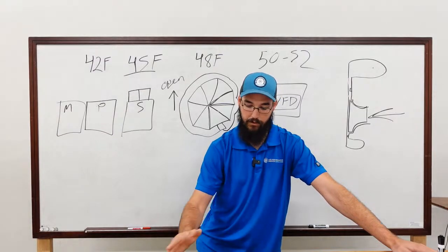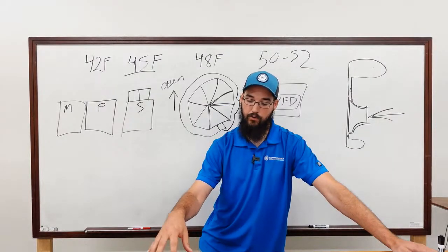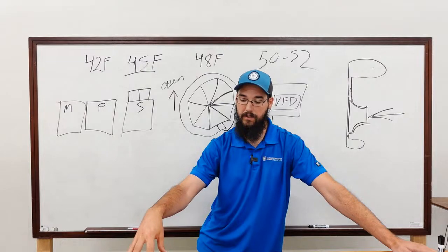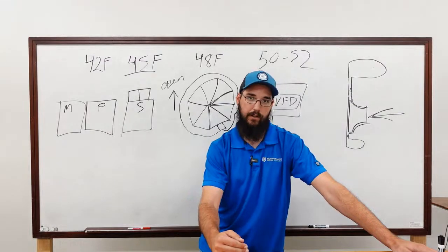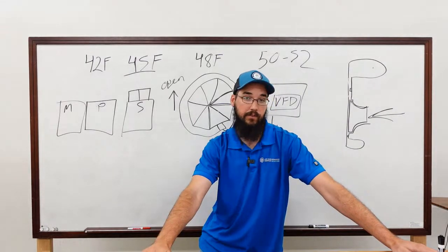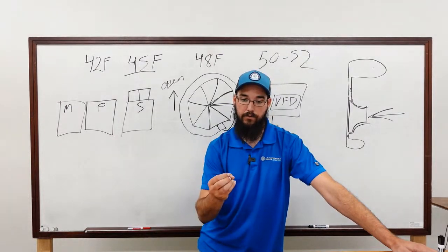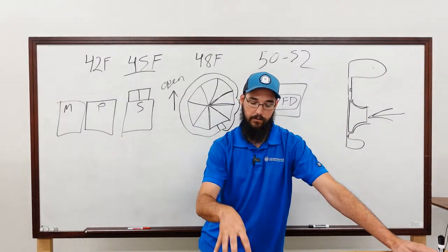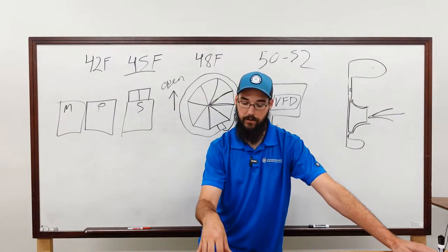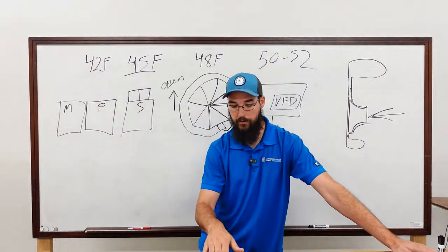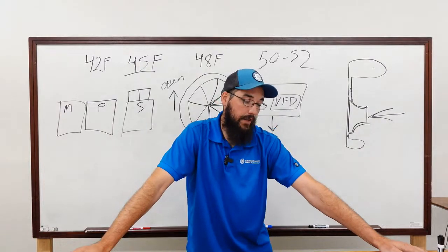Just precautions. Anyway, if you don't do that, whenever you're doing the recovery and you start to pull the system down in pressure, which is causing your saturation to drop, you'll get down below freezing in saturation and still have a significant amount of liquid refrigerant, and you can damage, expand, rupture the tubes in there and create a world of a mess for yourself. I mean, if you want a good experience of something you never want to do again, try that. You don't want to freeze the tubes.